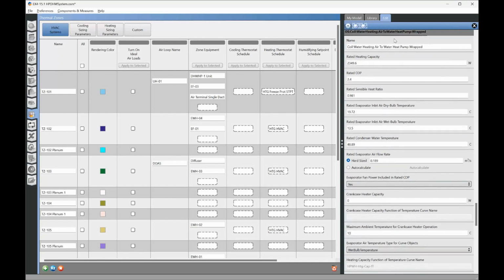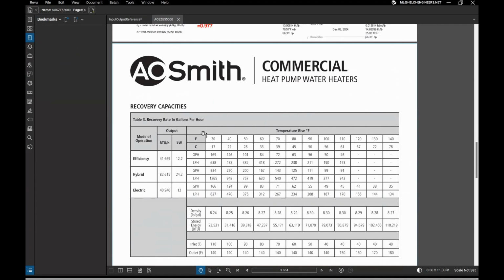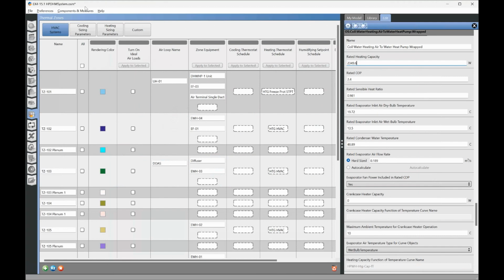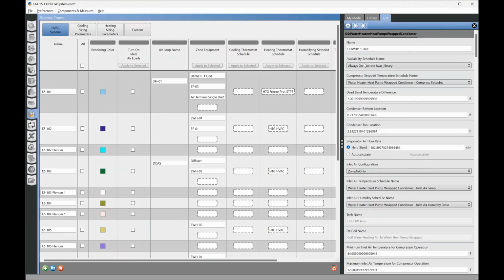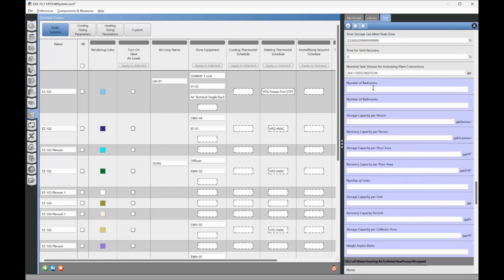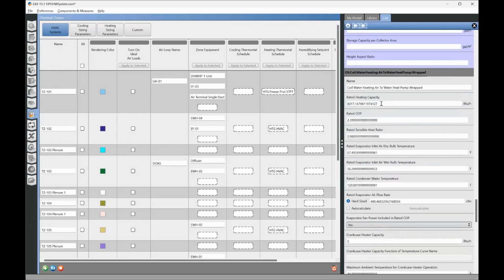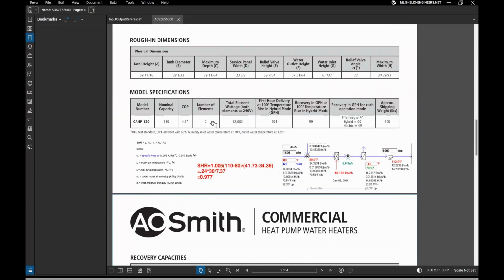The next object is the compressor itself. So this is the rated heating capacity of the compressor. And if we go back to the information on this, it looks like during efficiency mode, that is when it's using the compressor only, it has 41,669 BTUs an hour. We'll change back to English units. Its rated coefficient of performance is 4.3.